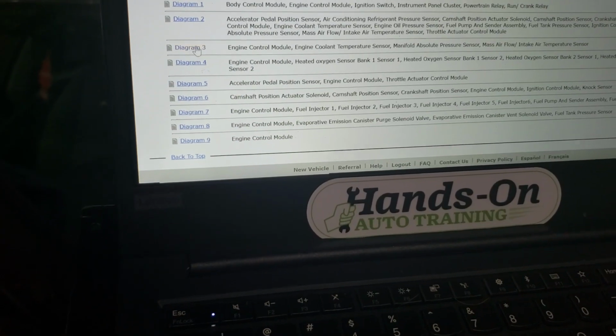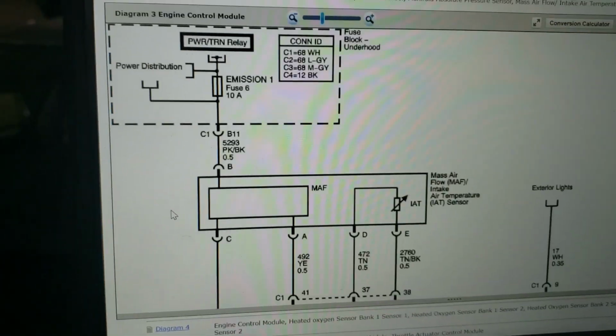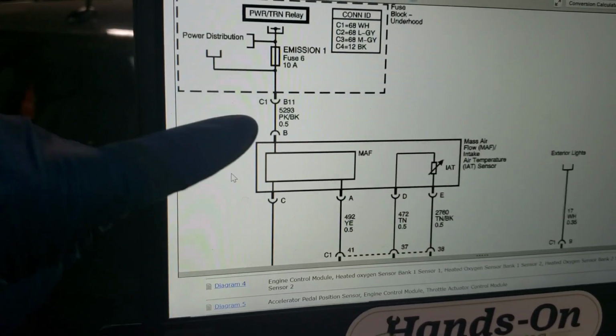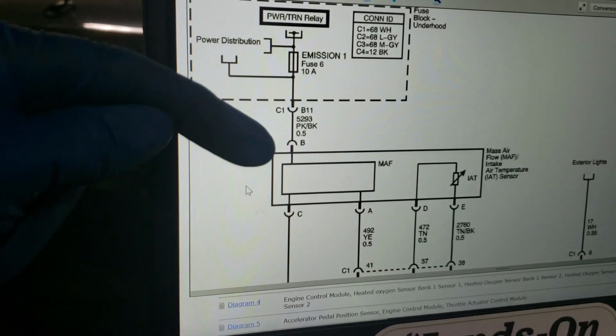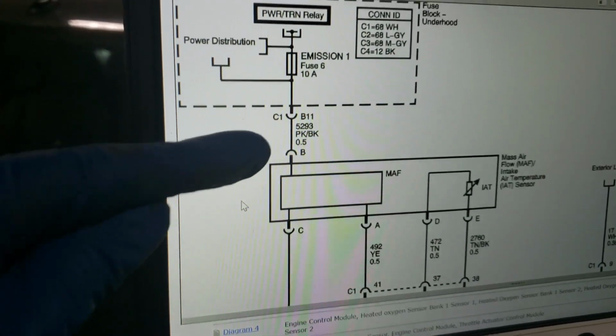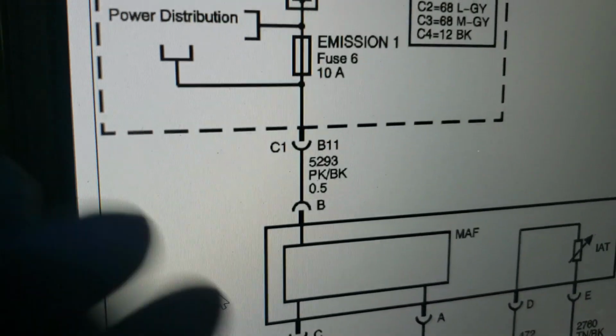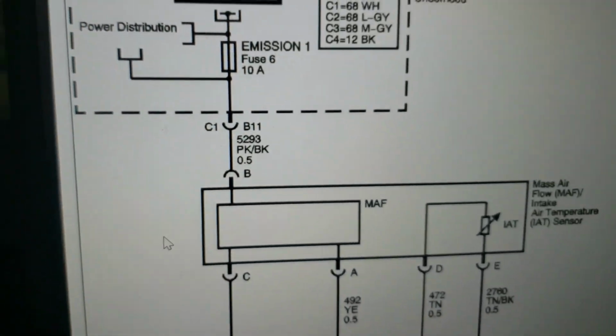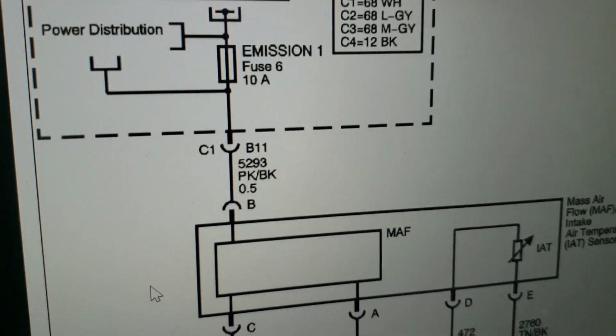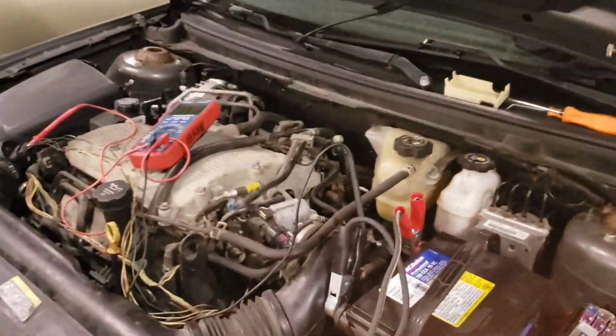Where did it go? Number 3. So we're going to be putting our voltmeter back probe here and the other lead there. What we want to see is a very low voltage. If we have anything above like a tenth of a volt or more, there's a problem in that circuit. So I'm going to try to test that.